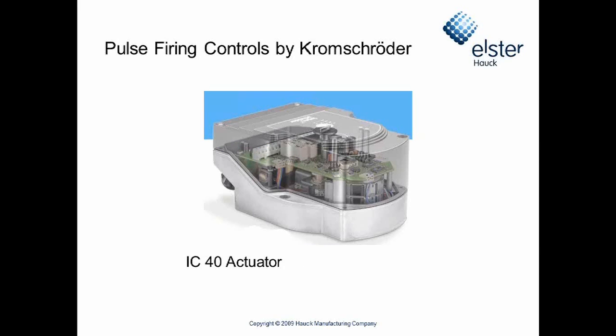If you need multiple points of control or a complex control scenario, instead of going with a solenoid-actuated butterfly valve, you can go with the Kromschroder IC actuator. Again, this actuator is designed for pulse firing. It will pulse at 7 seconds. It won't go down as low as 6, but it will do 7 seconds, and it will take the high duty cycle. This will allow you to do extremely complex pulse fire applications.